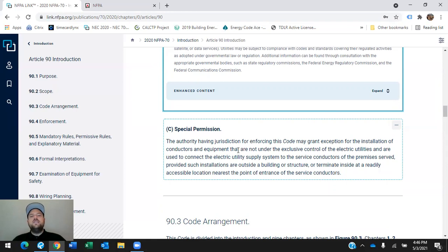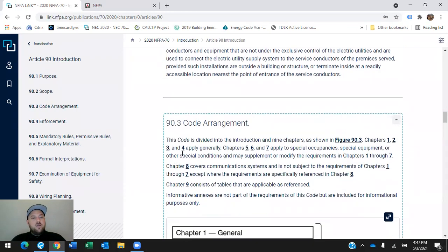So this section tells us the AHJ has the ability to allow an installation to not follow the code if they deem it a safe installation. They have a lot of power. That's a special permission that can only be granted by an authority having jurisdiction. It's typically not something we come across—we usually just go by the code, and the inspectors know the code. I've never seen a special permission myself. Perhaps some of you, maybe those who've been in the trade longer, have seen it, but I have not.